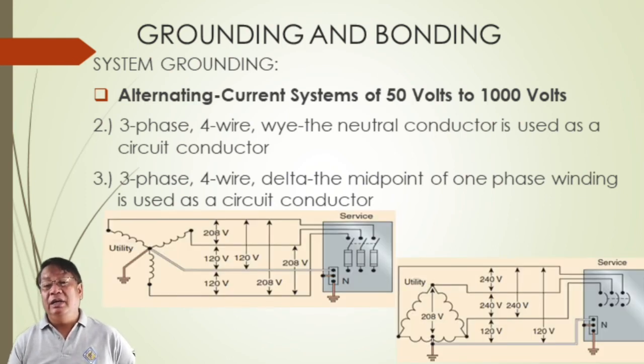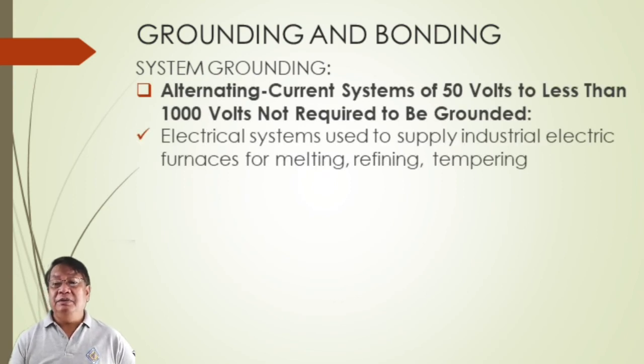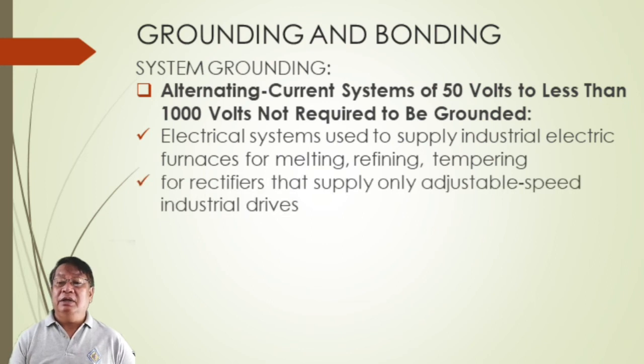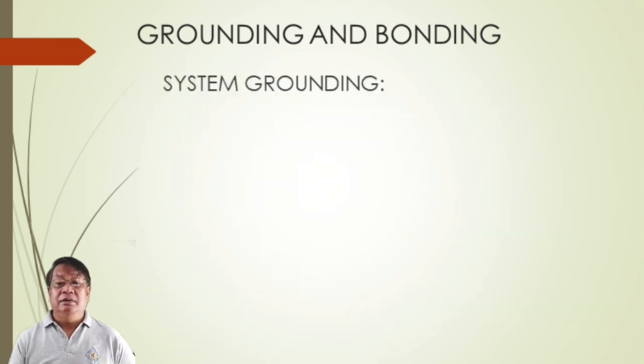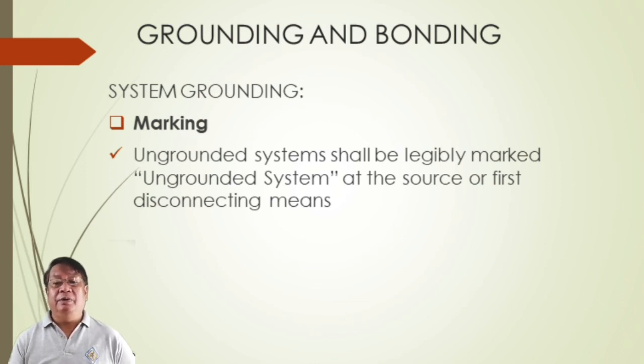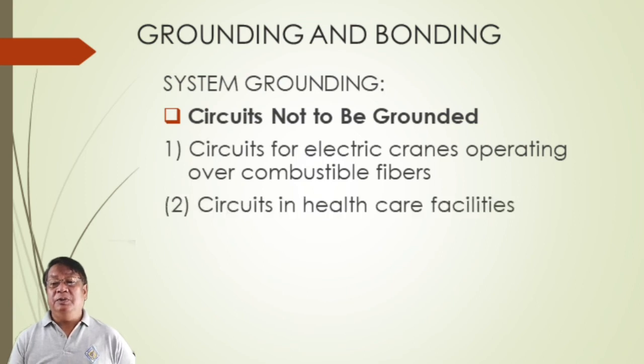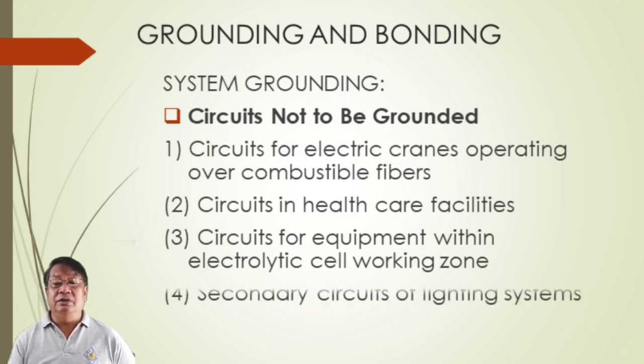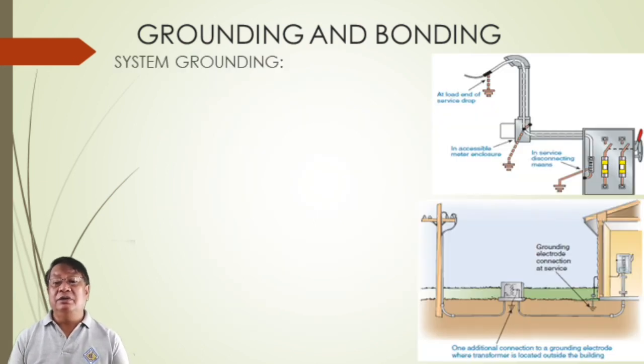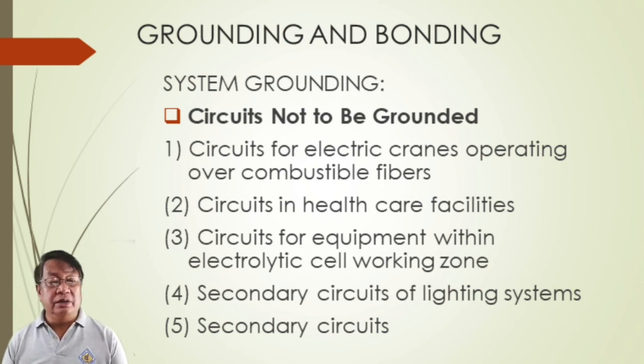Electrical systems used to supply industrial electric furnaces for melting, refining, and tempering using 50 to less than 1,000 volts are not required to be grounded. Circuits not to be grounded include: circuits for electric cranes operating over combustible fibers, circuits in healthcare facilities, circuits for equipment within electrolytic cell working zones, and secondary circuits of lighting systems.